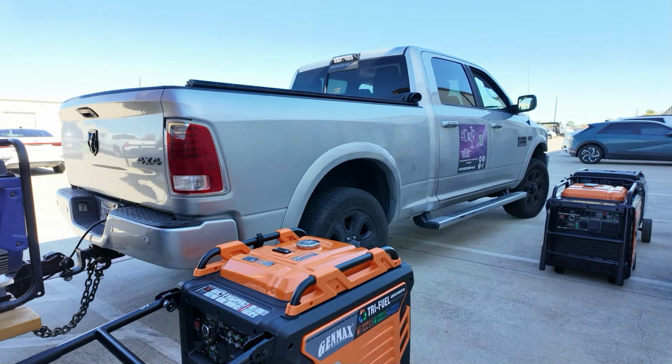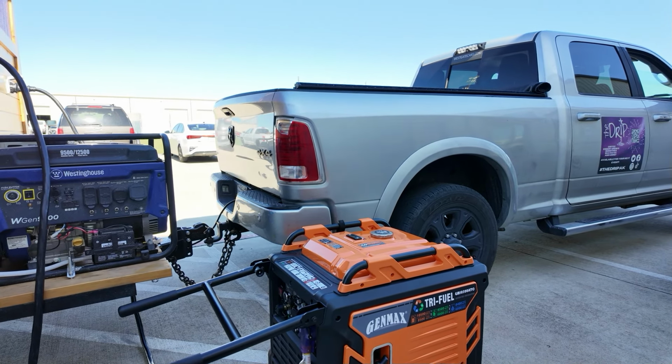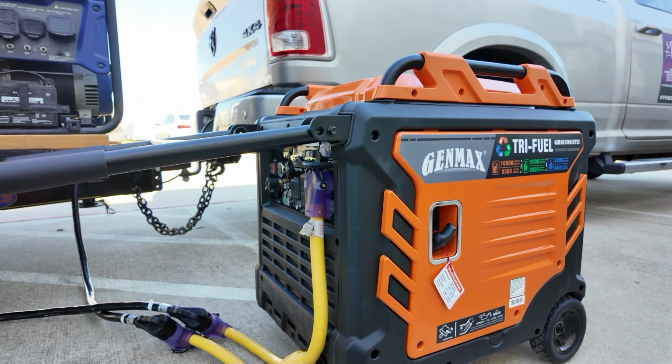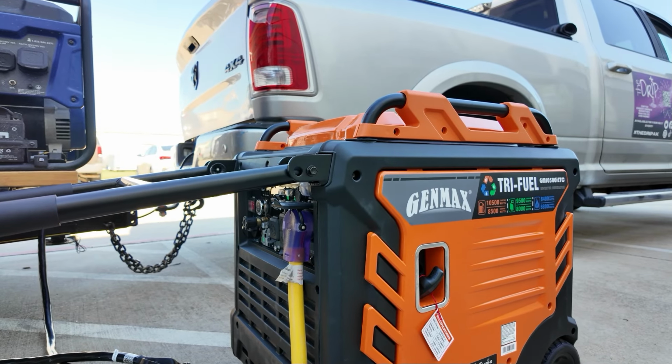All right guys, so the 10.5 does handle it. It gets all the way up to about, I would say, 80%, which is right where we want to be, but without the shaved ice. Once he turns his shaved ice machine on, that takes it over the limit.